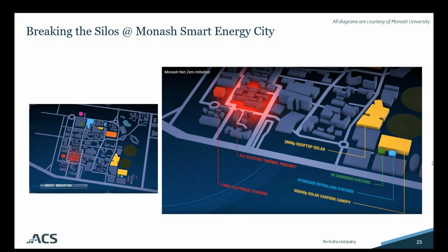Monash University has challenged the traditional way of operating a grid. Basically, they decided to run their network with the coordination of variable loads, renewable energy generation, and Australia's largest behind-the-meter energy storage system. From the initial idea, the Smart Energy City at Clayton campus was meant to show to the power industry that DR penetration and load control can be used to guarantee the same power quality constraints the utilities must comply with. So the initial scale and the scalability is one of the driving parameters in every technological choice that we did in the project. Monash, by the way, is also leveraging the flexibility allowed by the absence of a regulation that applies to their grid. And with the collaboration of the Faculty of Law, is reporting to the regulator the opportunities the changes in the regulation may bring to the whole industry.